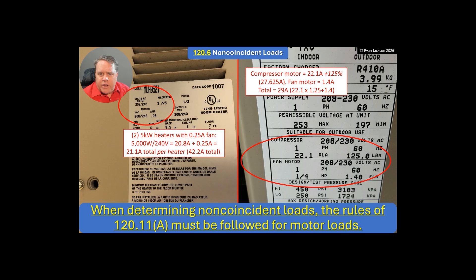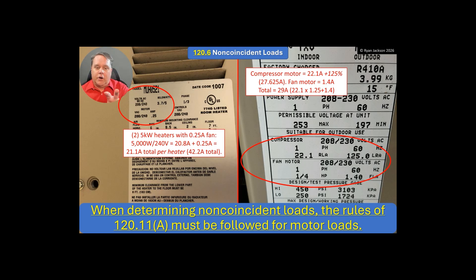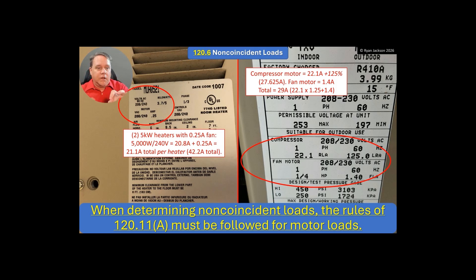When determining non-coincident loads, the rules of 120.11(a) must be followed for motor loads. I'm not going to get too deep into 120.11(a), but what it says is when you're doing your motor load calculations, generally speaking, if you have a motor and other loads or multiple motors, you're going to take the biggest motor at 125% plus all of the other loads on that circuit.